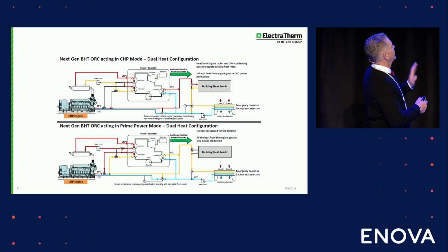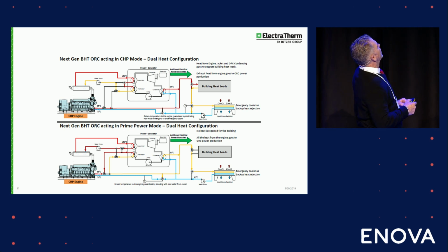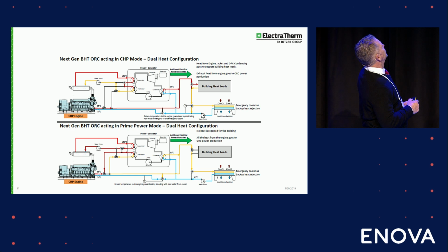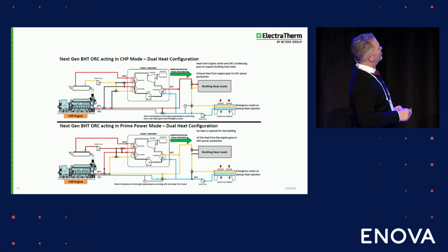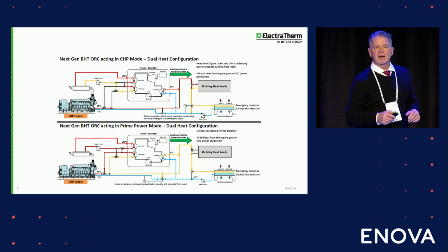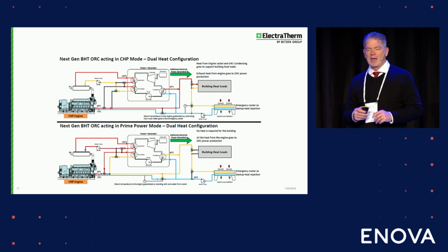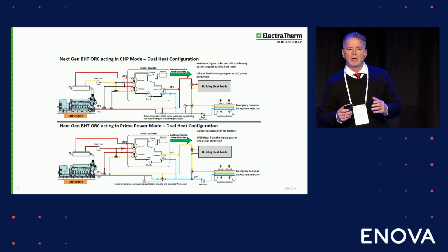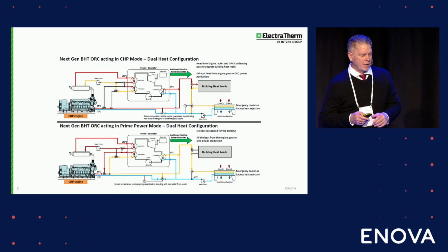Here's another example of running in dual heat load mode: exhaust into our evaporator, jacket water into our preheater, separating those loops. We consider this a real CHP mode. We can also go prime power, where power production is most important and building heat is secondary. I hope that gives you an idea of our flexibility in how we can run and where.